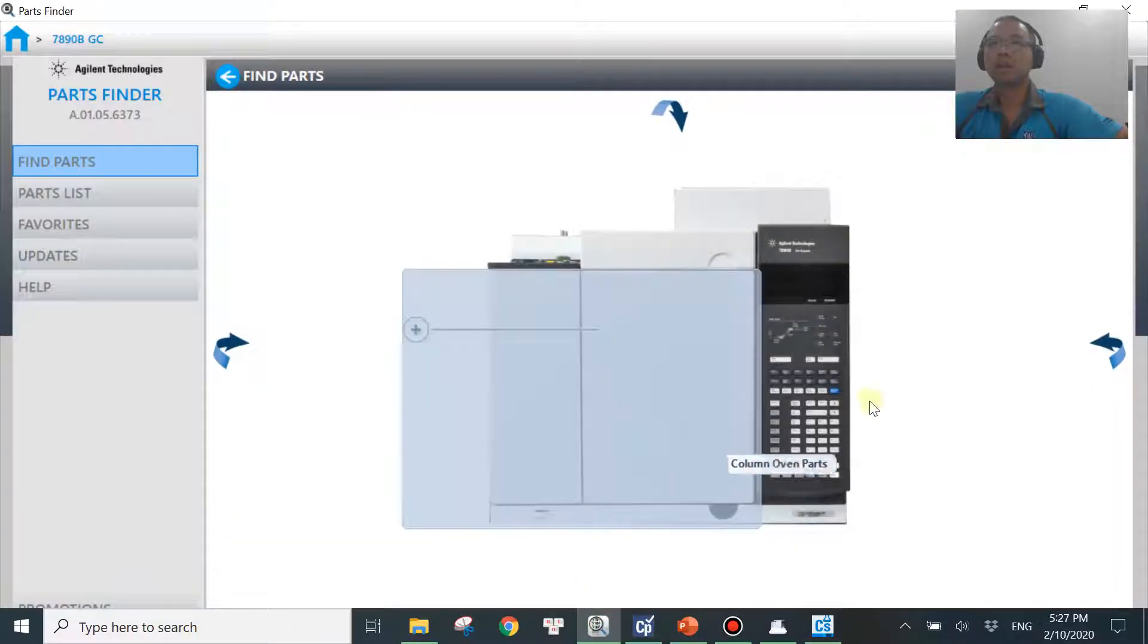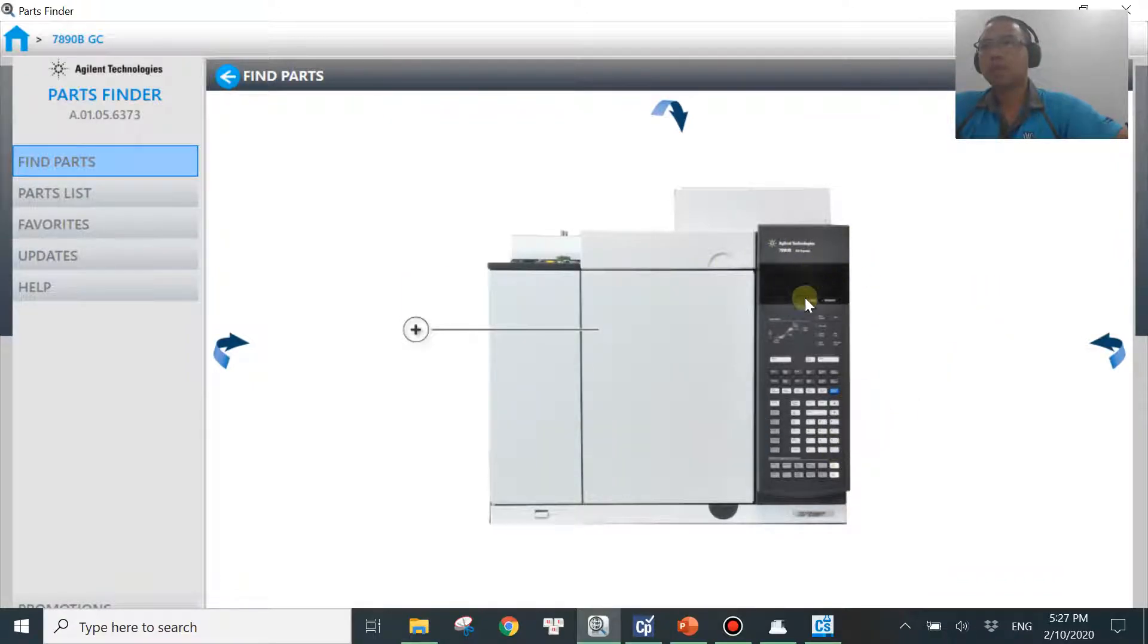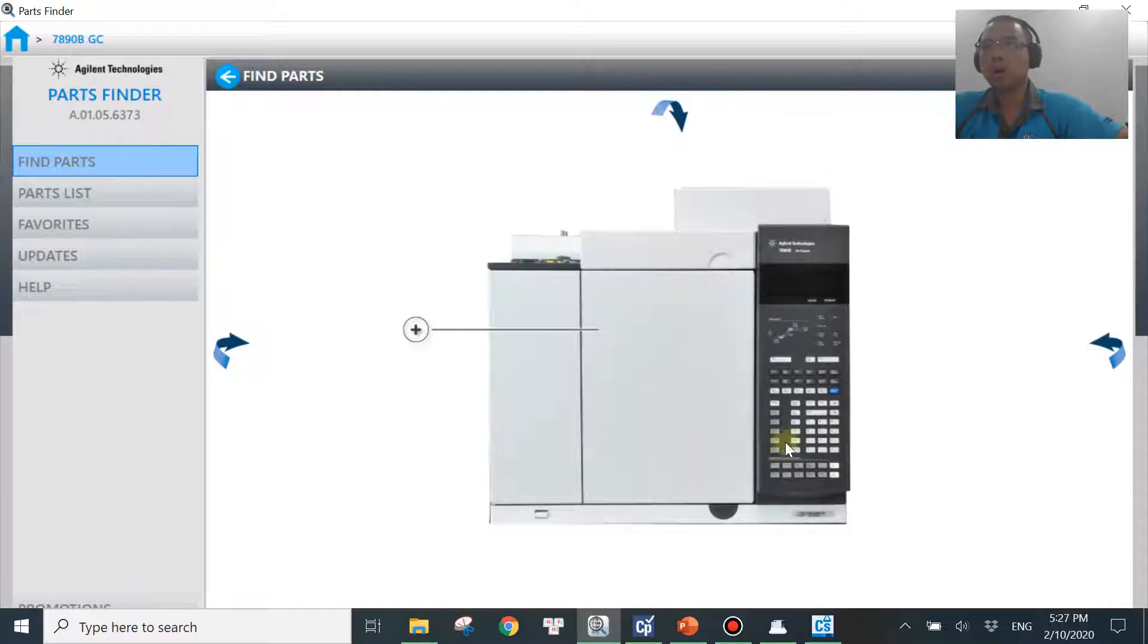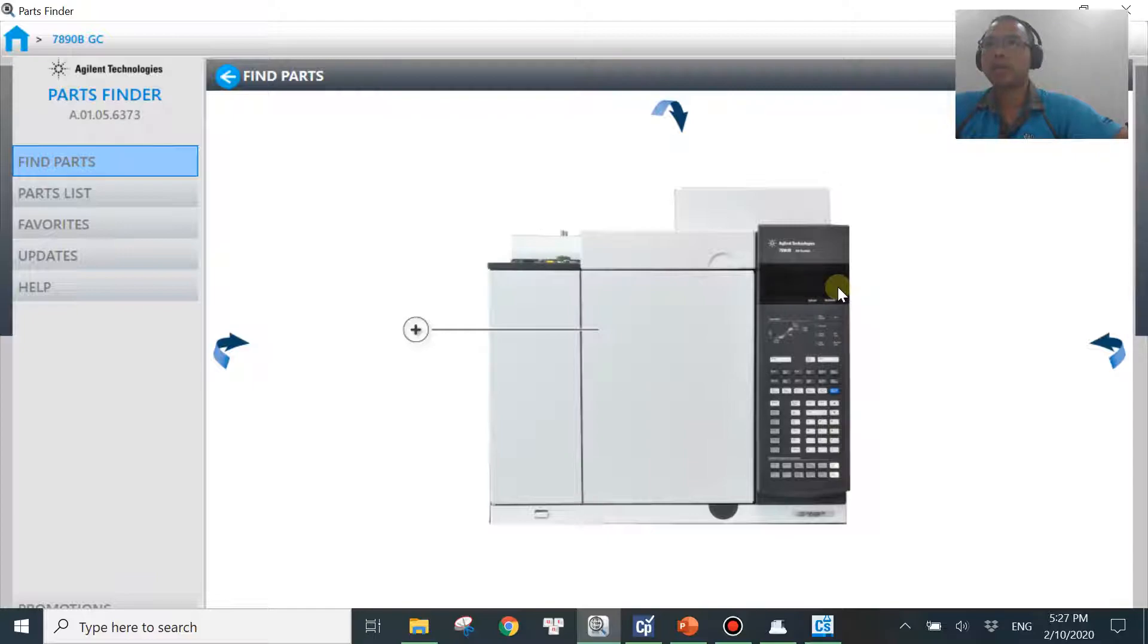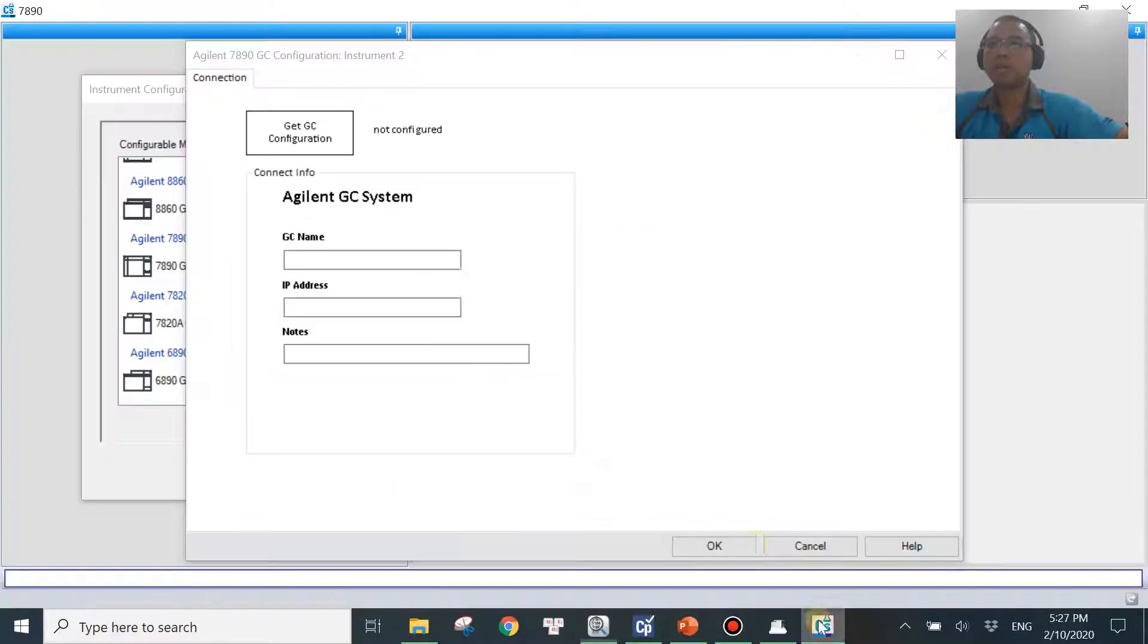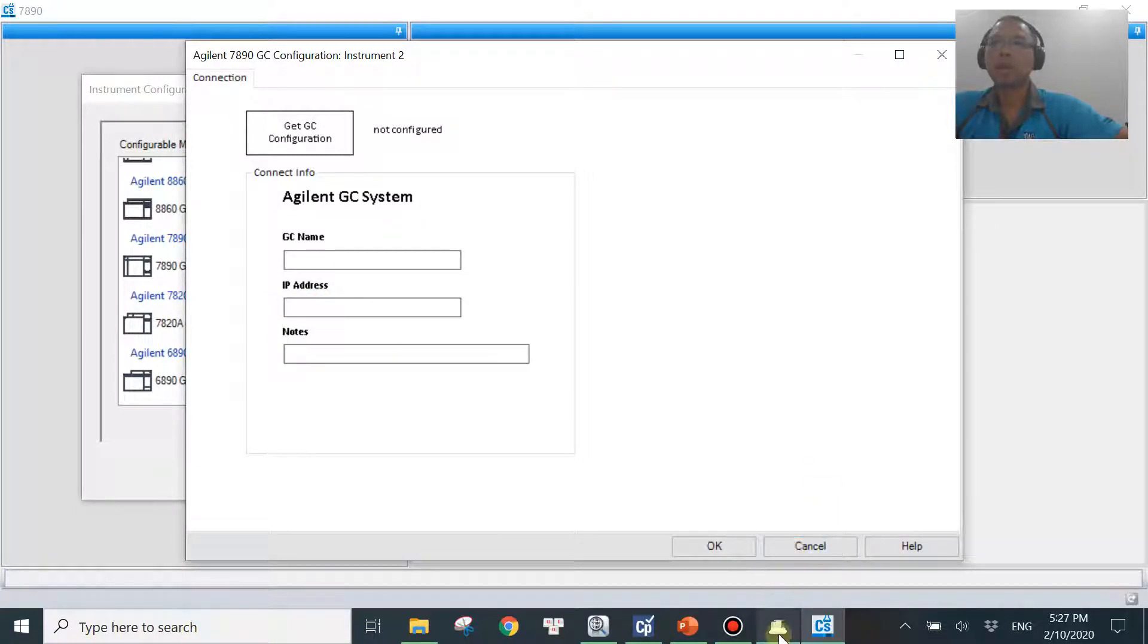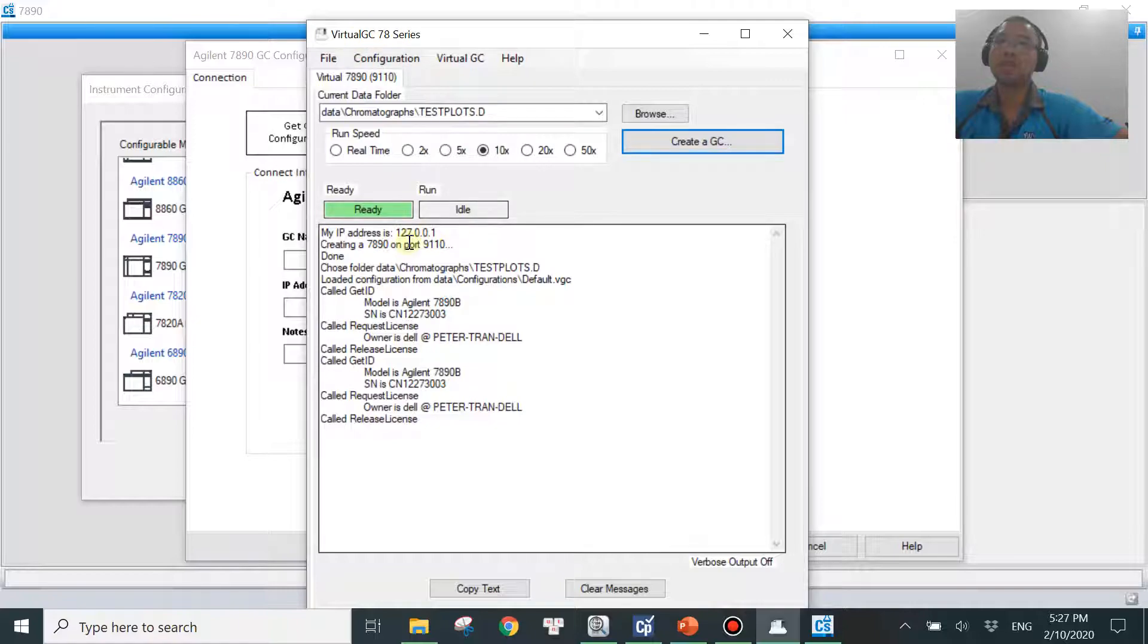So this is the outlook of the 7890B GC. If you want to find the IP address of the instrument, you hit the option button right here. And then you will be seeing calibration, communication, things like that. Then you hit the arrows over here to move down to communication. Hit the enter button. And then you'll be seeing the IP address display on top here. And once you see the IP address, simply enter those IP address into this box over here. So for my case, because I don't have a real GC connected right now, I'm using a virtual GC version.